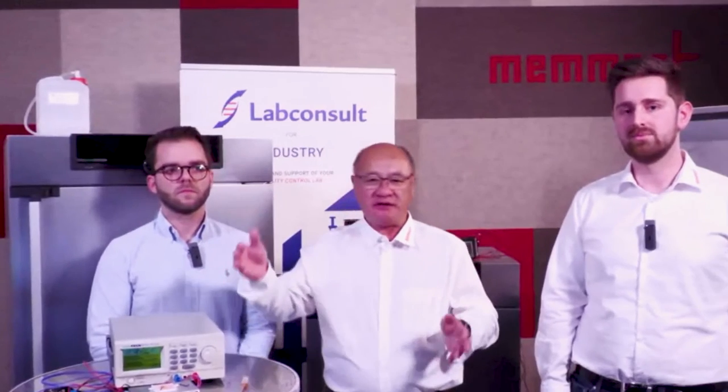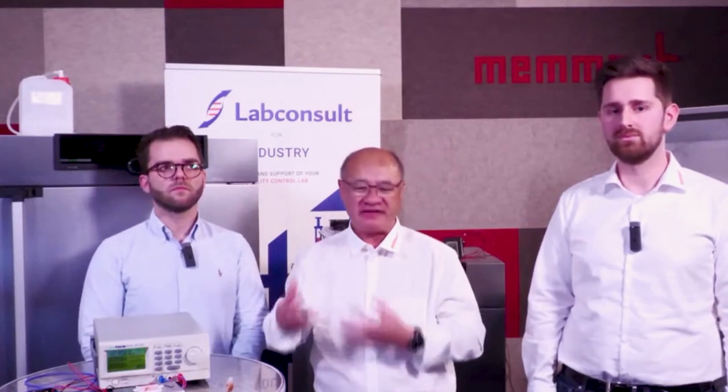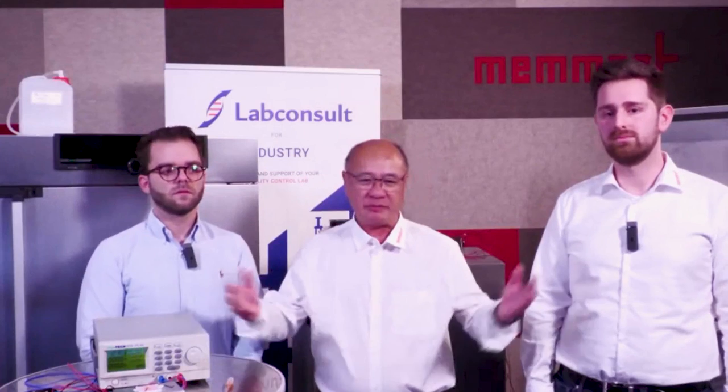To summarize: there is no bad technology. Peltier works very well — it depends on your application. If you are working more or less between 5°C and 50°C, Peltier technology is a really good choice. If you are working around 20°C, it is the best choice because the energy consumption is really, really low. But if you are working around 0°C, minus 10, minus 20, then compressor is the best technology. It depends on your application.